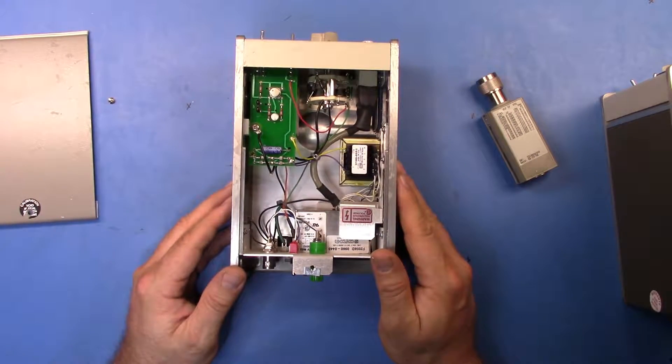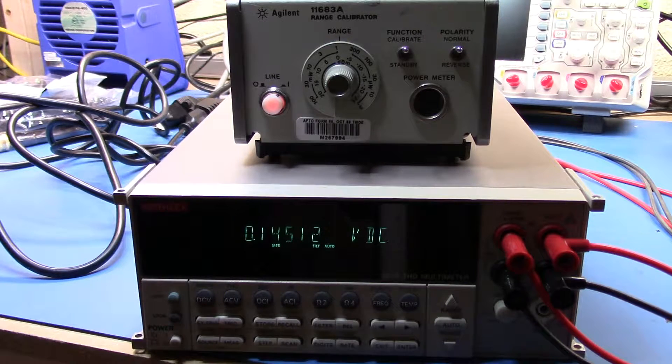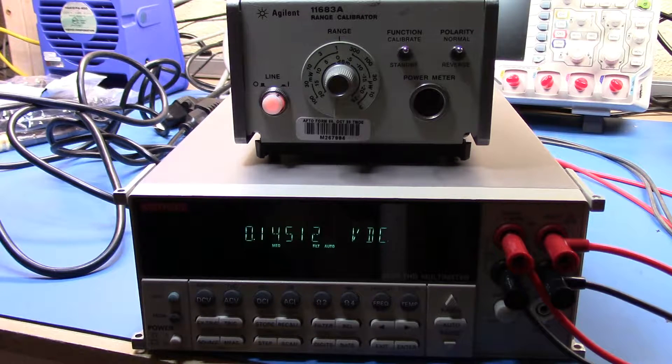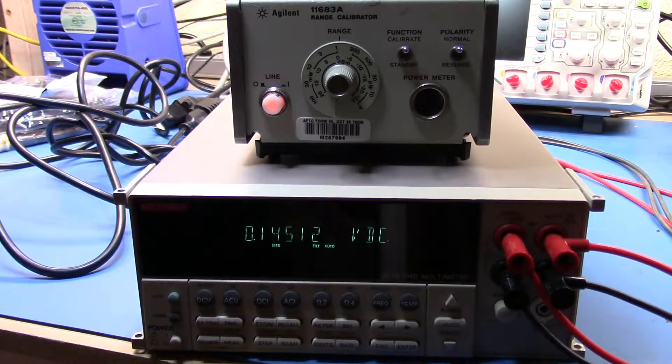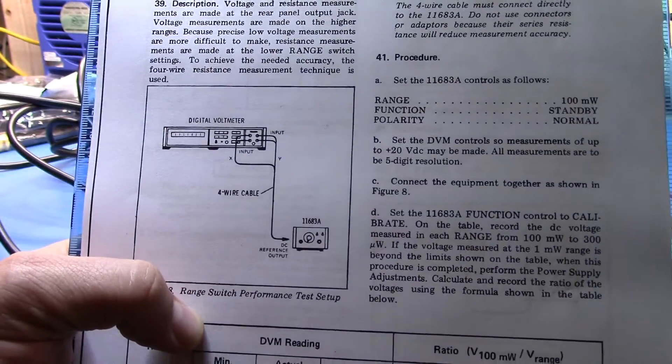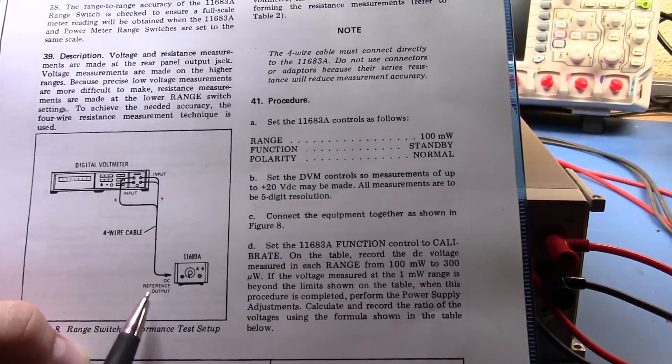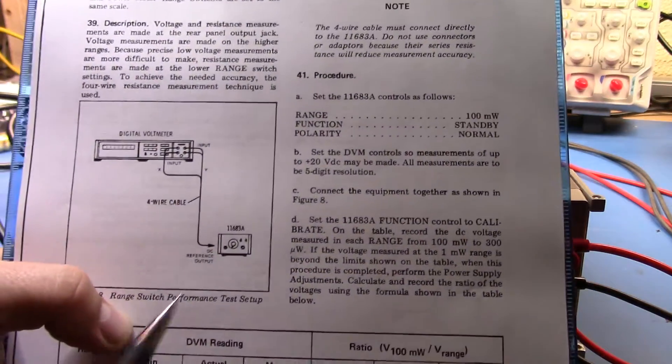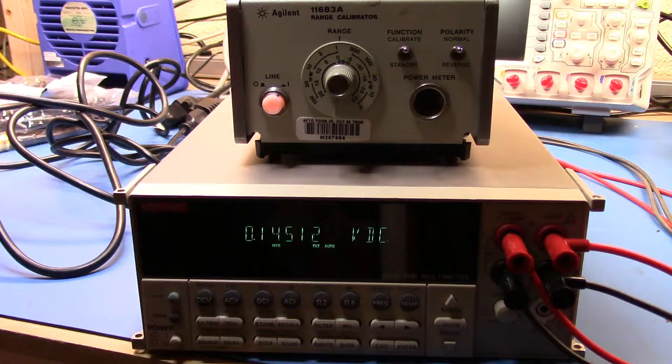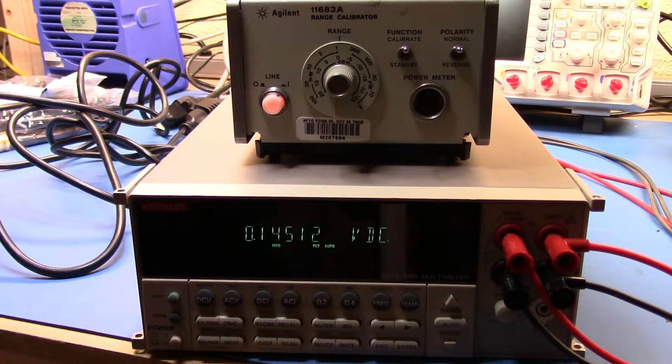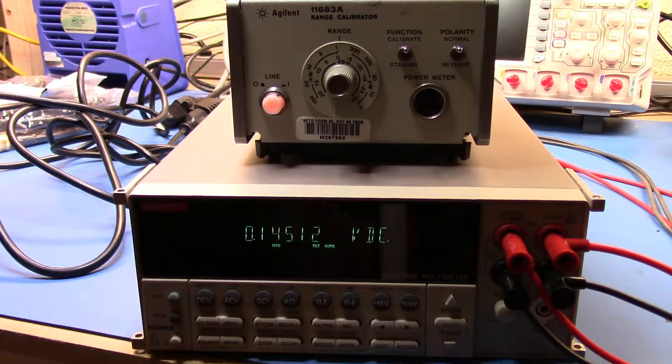Let's power it on and see how it stacks up to its supposed reference voltages. Okay, I'll let that warm up for an hour or so so that we can go through and see how accurate it is. What we can see is, if we bring in here, I have this set up exactly as we have the outline here. We have my Keithley 2015 connected via a four-wire Kelvin style cable into the DC reference at the back there.